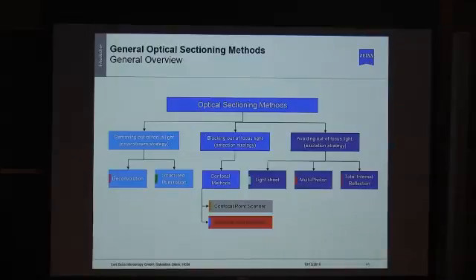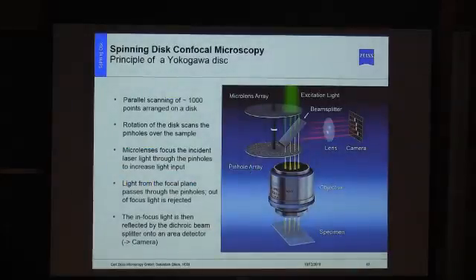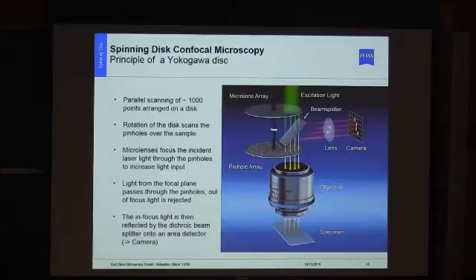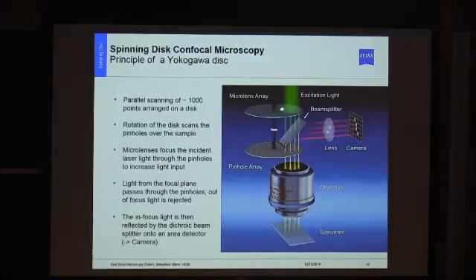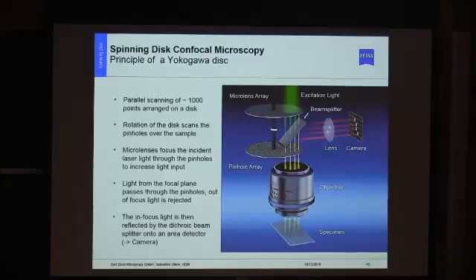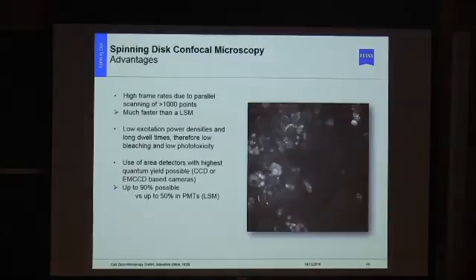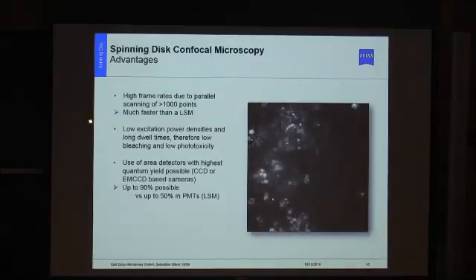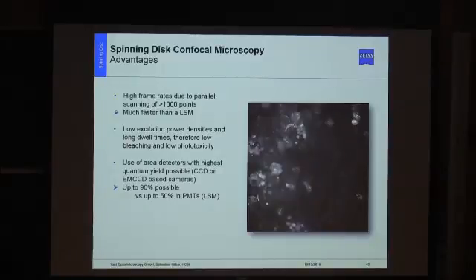Moving on to spinning disk systems — another detection strategy where we block out-of-focus light. The spinning disk system has two disks that rotate synchronously. Laser light passes through a microlens array, where it is focused onto the pinhole array. Light from the pinhole array exits through the objective onto the specimen, returns back, passes through a beam splitter, and falls onto the camera. This system scans more than one thousand focal points more or less simultaneously in parallel fashion, achieving very high frame rates.